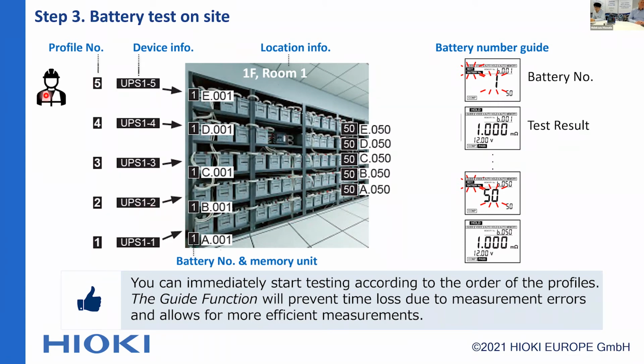The test operator just presses the guide button, which is a new addition to the BT3554-50, and selects the start profile number and threshold. The battery display will show the battery number, so the operator can check the number while taking the measurement.